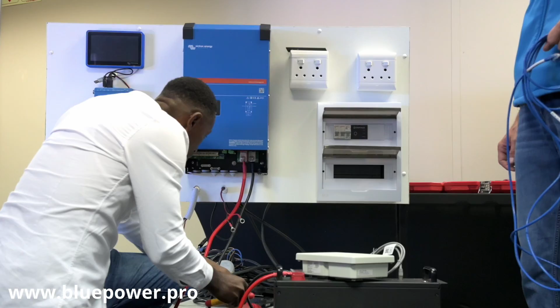Okay, so on battery compatibility, if we go on the manual, we can see on the CAN bus wiring between the battery and the GX device, it indicates that it uses a VE CAN Type A cable. This is also a pre-made up cable, available from Victron, coming in 3 and 5 meter lengths now, pre-made up.